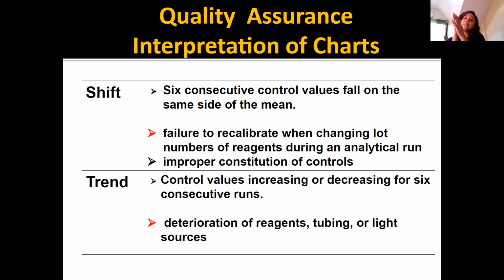So sa reagent nyo guys, may mabasa kayong lot numbers. So, just check. Kung pare-pareho yung binili nyong lot numbers, no need to calibrate. Ibig sabihin, sabay-sabay sila sa pag-manufacture. Kung magkaibang lot number, magkakaiba sila ng pamilya. You have to recalibrate your machine. So, kailangan mag-run ka ulit ng controls.